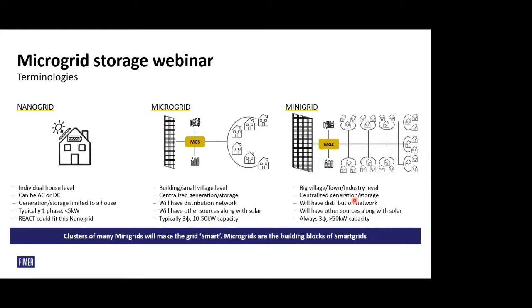Microgrid is something which will have centralized generation and centralized storage, with a small distribution network, not more than 4 to 5 kilometers, usually at the LV level itself, the low voltage level. It can also have some additional sources like a biomass generator in order to have an optimal energy mix and cost of power. Mini grid is, I would say, a microgrid at a bigger scale in terms of power. It can sometimes have other sources like diesel generators. So I would say a big village or a town or a factory can be called a mini grid. Either way, mini grid and microgrid usually mean the same.